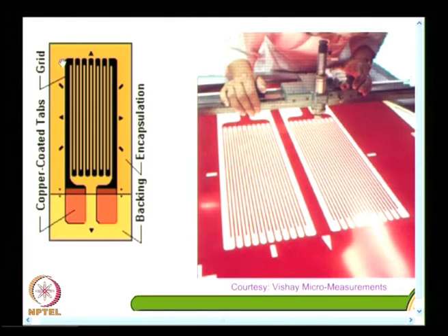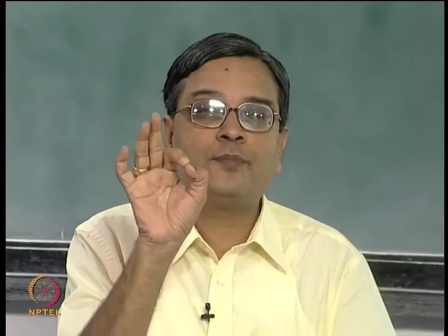It would have some sensitivity for strain along the transverse direction too. So, we have to bring in the engineering approximation. See, if I have a wire or if I have a magic material, I just take one speck, put it at the point of interest and solder it, there is nothing equal to it. We do not have one speck of material to give you strain at a point of interest.